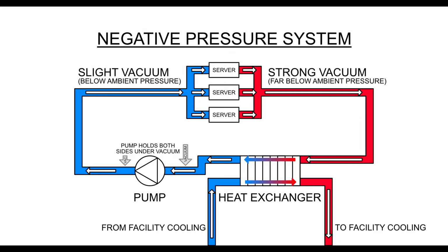But in a negative pressure liquid cooling system, it doesn't matter where a leak occurs, because coolant cannot leak out of the system. Even with multiple small air leaks, negative pressure liquid cooling systems can keep on pumping, with no risk to the servers.